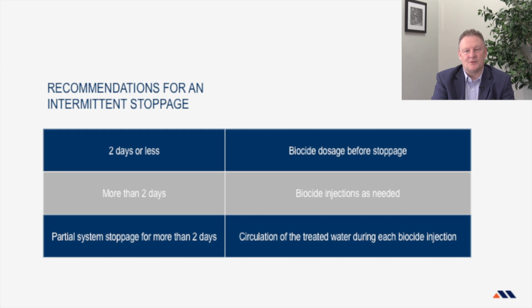The same applies for partial system stoppages. For example, for repairs, where the water in the area becomes stagnant, it must be treated regularly to prevent excessive proliferation. Another example: swapping recirculation pumps will cause water stagnation and promote bacterial growth.